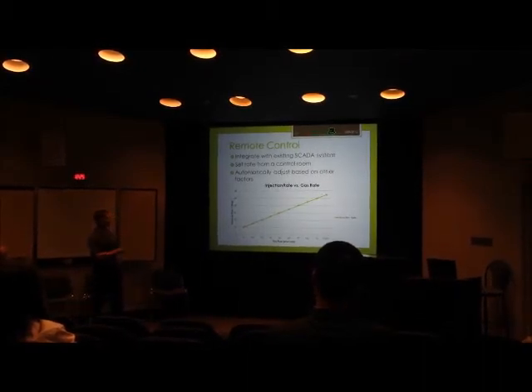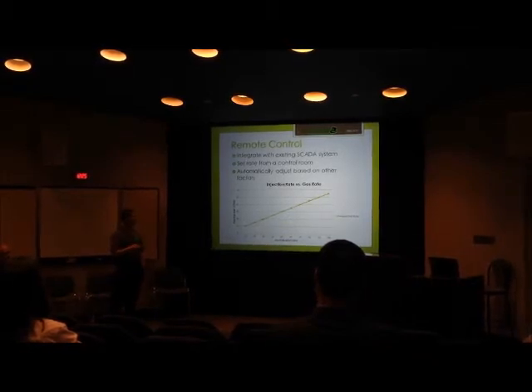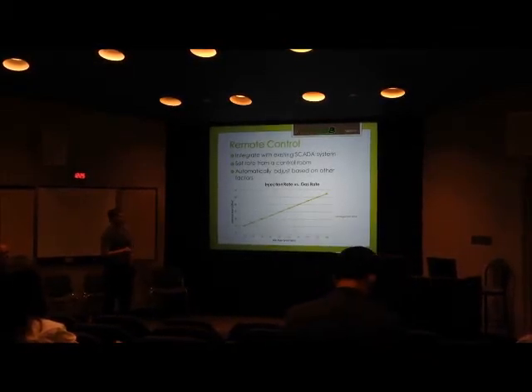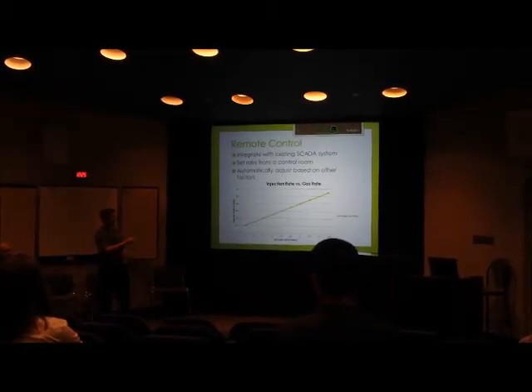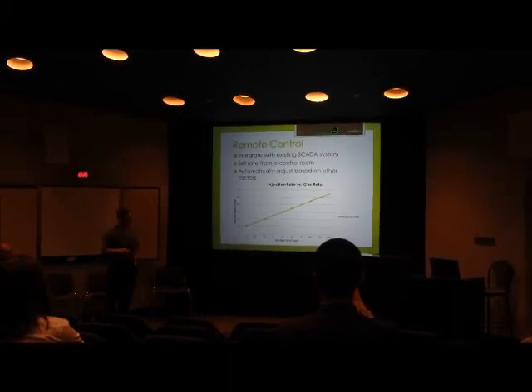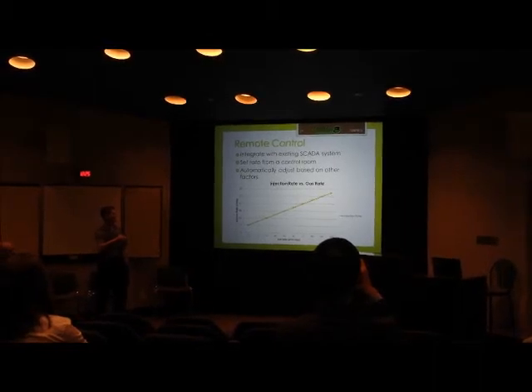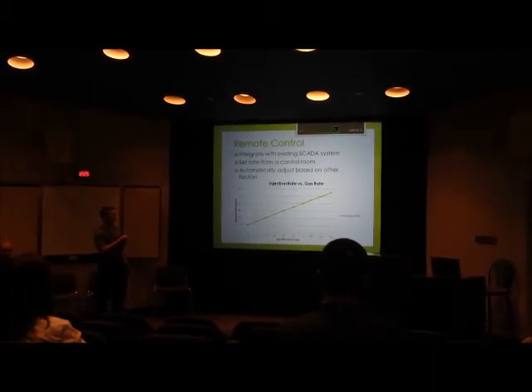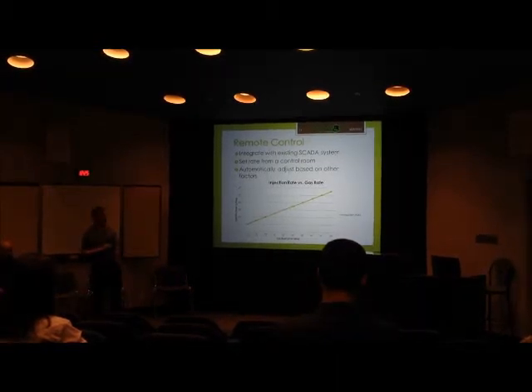That's for gas rates, liquid rates. If this was off of an oil battery or something like that, and this was wax solvent, maybe at 80 cubes a day, you need 40 liters wax solvent. But as some wells shut in or you're doing workovers, different things change. So basically, whatever numbers you're bringing in through SCADA, we can set this up, or the operators can set that up, change the endpoints, and you can automatically control off of varying conditions.